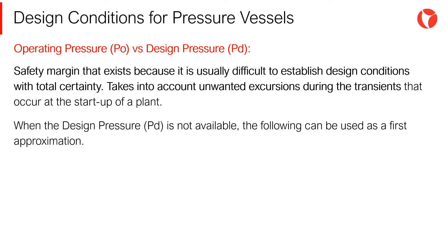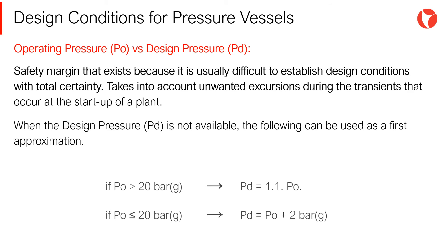If we need to design but only the operating conditions are known, a workaround could be as follows: if the operating pressure PO is higher than 20 bars, the design pressure is 1.1 times the operating pressure. Alternatively, if the operating pressure is less than 20 bars, the design pressure is the operating pressure plus 2 bars.